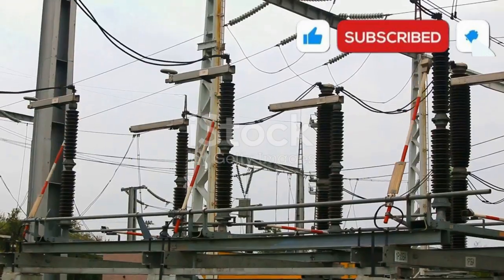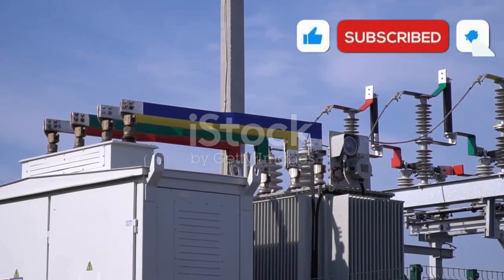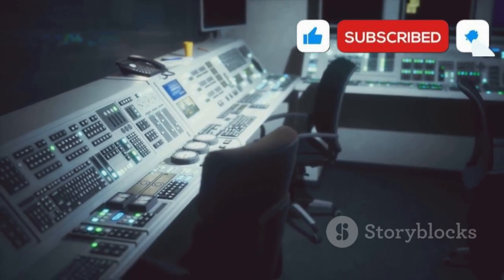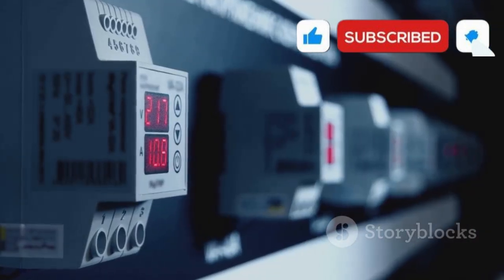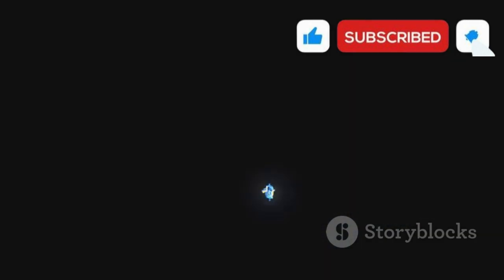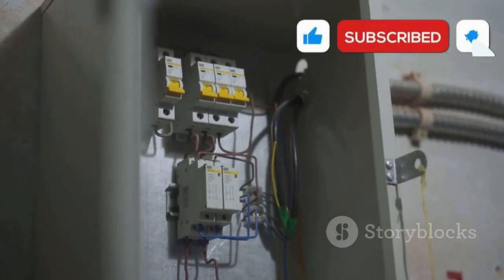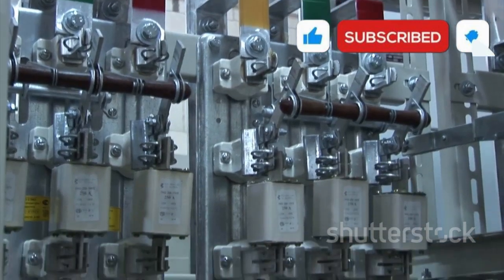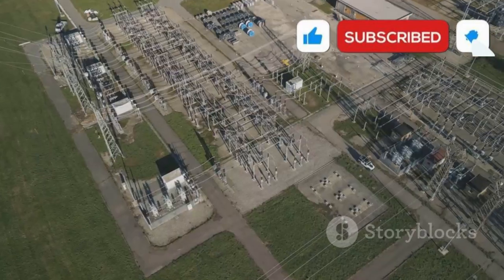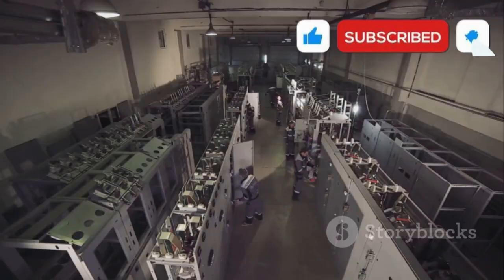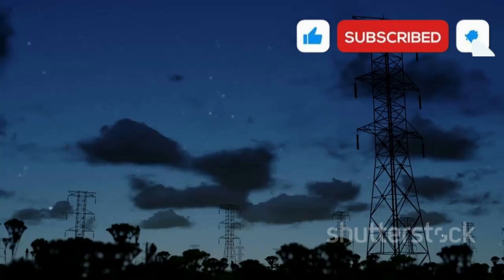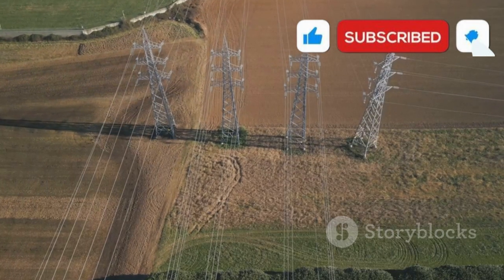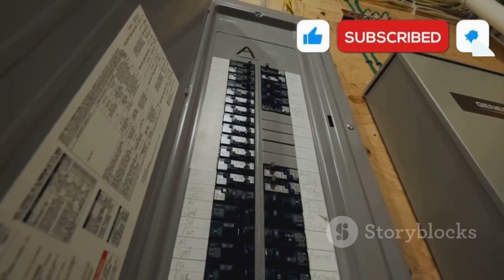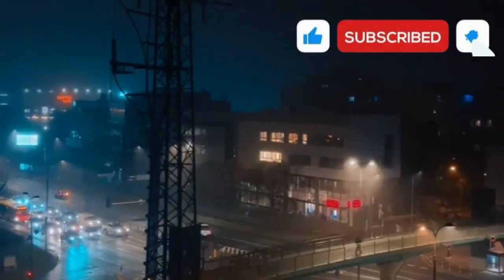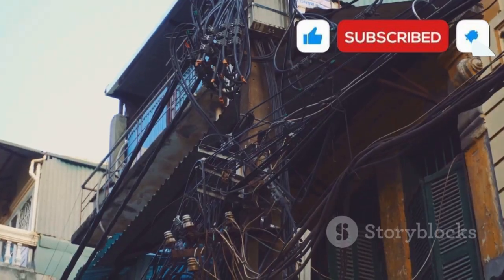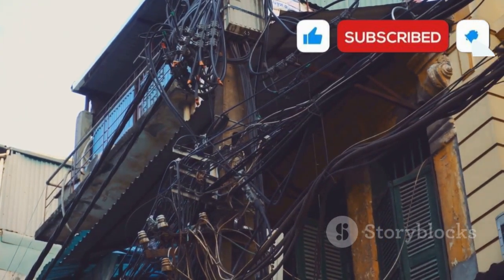into darkness. The grid's bodyguards are relays and circuit breakers, constantly monitoring for trouble. Relays detect abnormal conditions, overloads, voltage spikes, or short circuits, and signal breakers to act. Circuit breakers are fast-acting switches that isolate faults, preventing problems from spreading. These devices operate in fractions of a second, minimizing outages. They're deployed throughout the grid, from transmission lines to your home's panel. Most of the time, they handle issues so quickly you barely notice. Without them, the grid would be far more chaotic and unreliable.